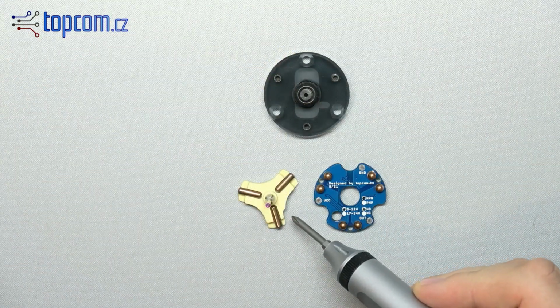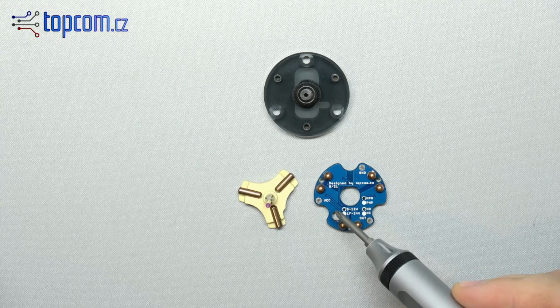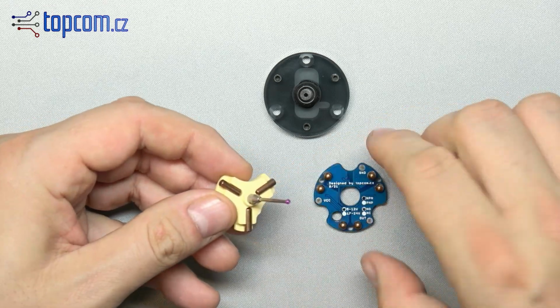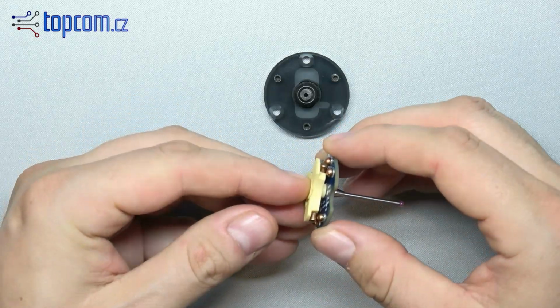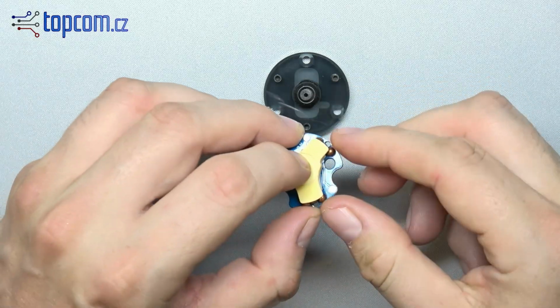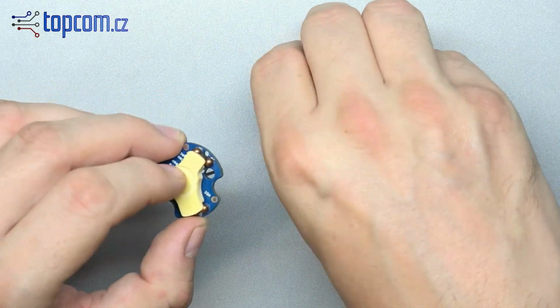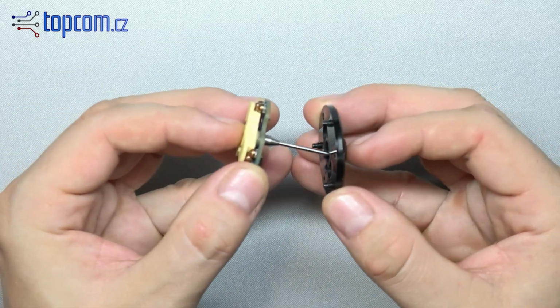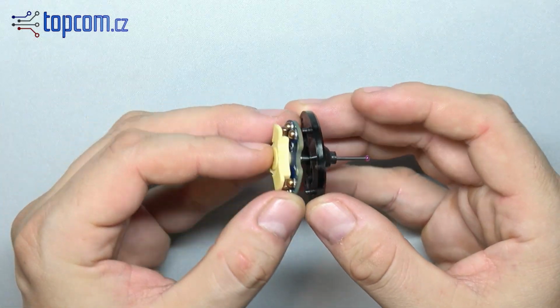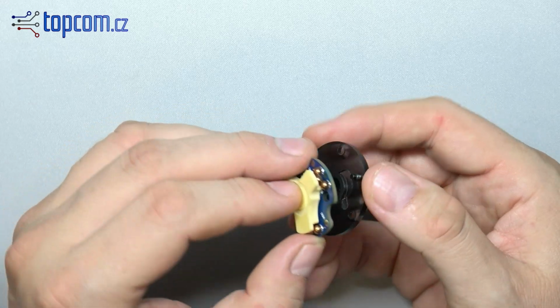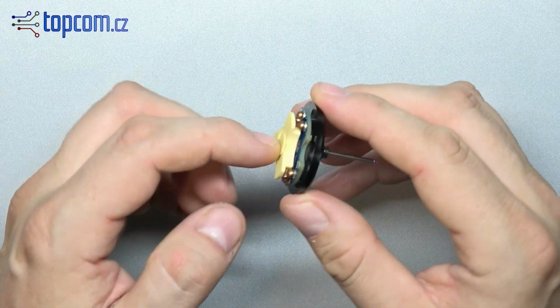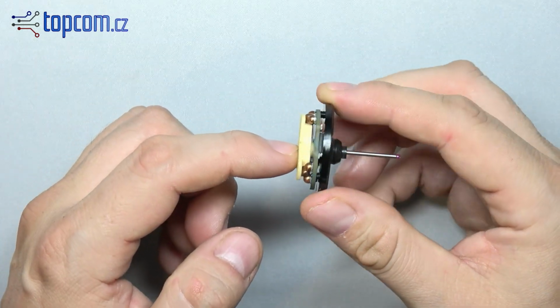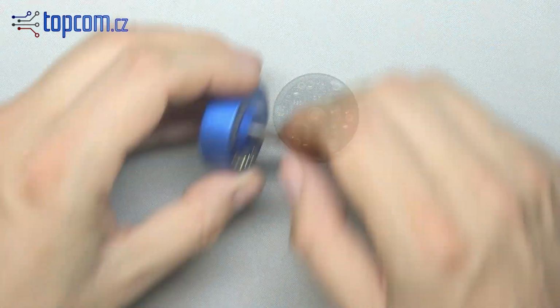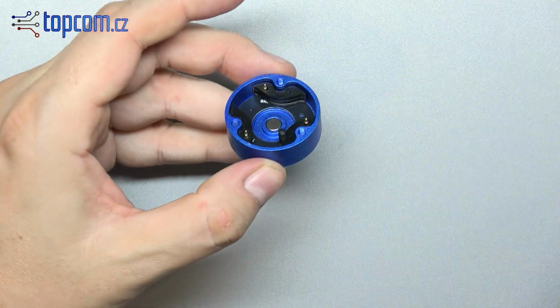During reassembly, pay attention to the unique shape of one part of the touch stylus, as well as the anti-rotation slot in the probe's base plate. These parts must be aligned together. Gently support the silicone seal with your finger and insert the touch stylus through it. Then rotate the PCB so that the IC on the PCB fits into the cutout in the lower part of the probe housing. Now it's time to assemble the probe.